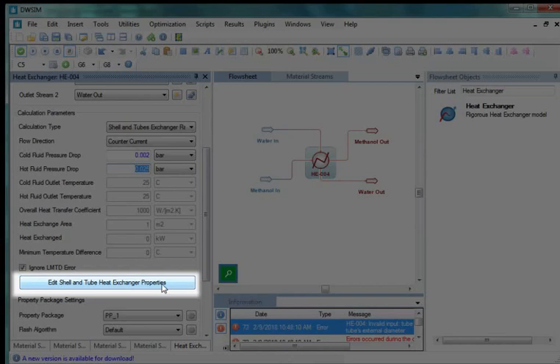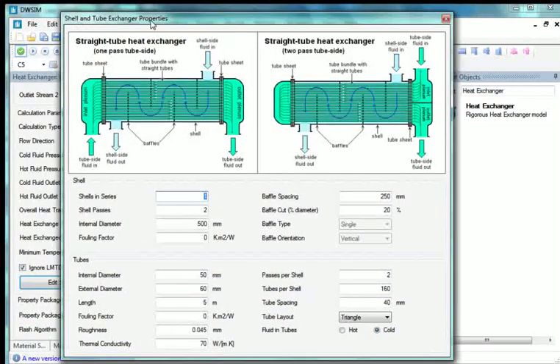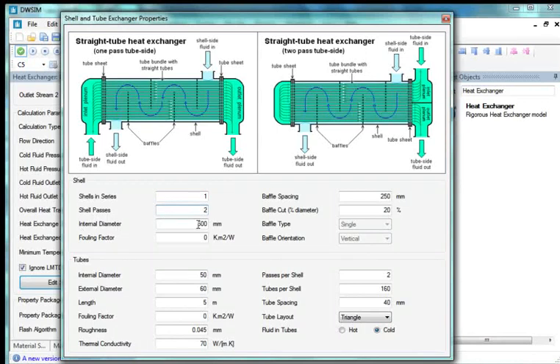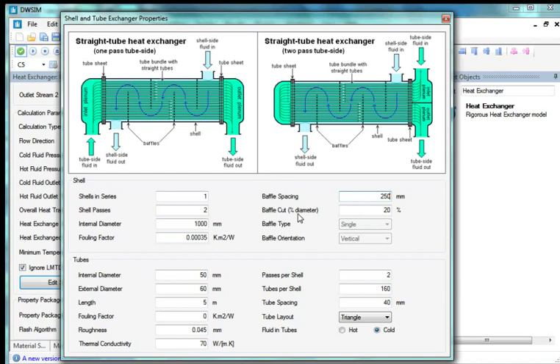Now we will enter the properties of the Shell & Tube Exchanger. Click on Edit Shell & Tube Heat Exchanger Properties. The Shell & Tube Exchanger Properties window opens. We will edit the Shell Side Configuration: set Shell in Series to 1, Shell Passes to 2, Internal Diameter to 1000, Fouling Factor to 0.00035, Baffle Spacing to 250, and Baffle Cut to 25. This completes the Shell Side Configuration.